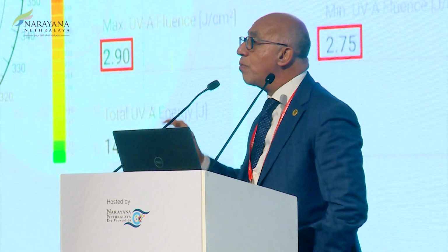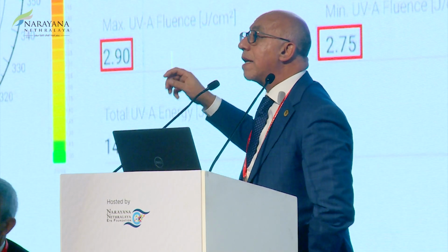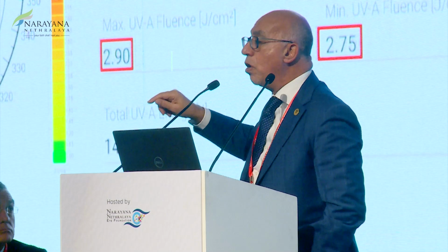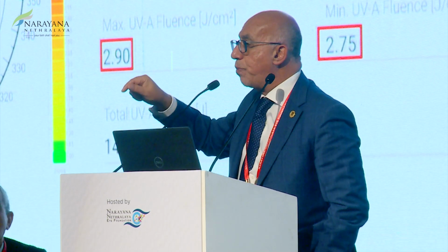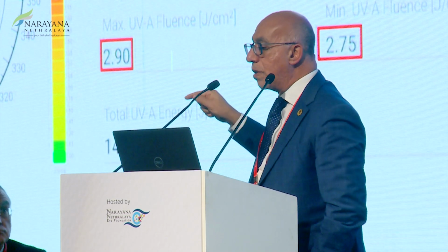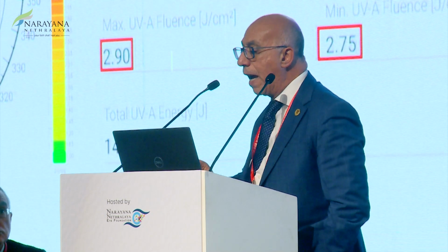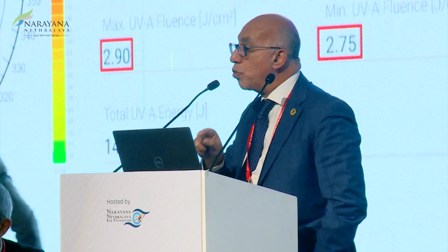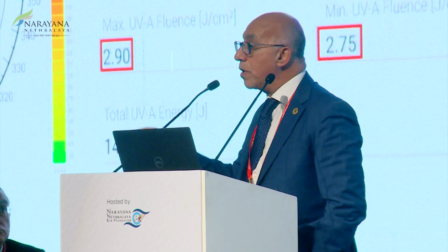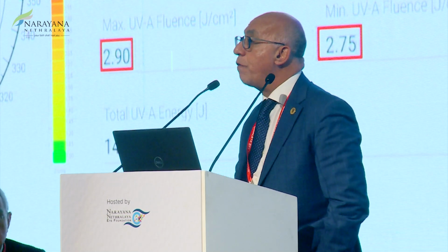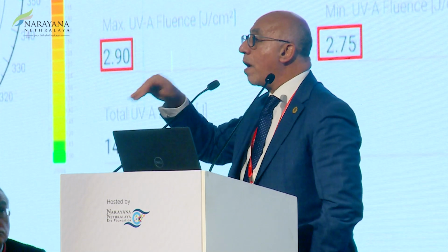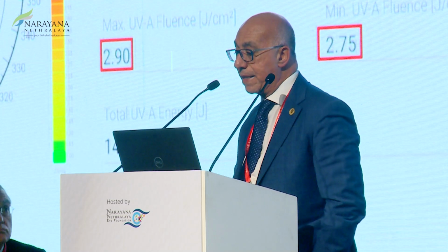So the power that will be delivered by the cross-linker at the end of the operation will again be fully customized to deliver the maximum energy at the thinnest point and then a variable energy to the transition point, varying from 2.9 joule to 2.7 joule in an 8mm zone. Fully customized, fully tracked in X, Y, Z axes.